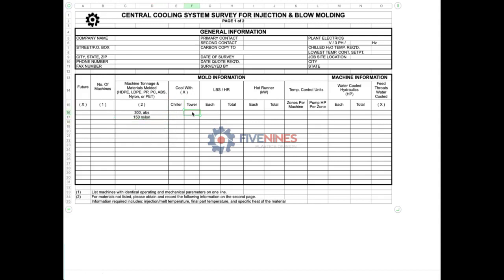You mark what it's connected to, whether it's chiller or tower, pounds per hour. So where you see 'each' here, you can list all of your 300-ton machines in this row and all of your 150-ton machines in this row. However, I suggest that you do it individually, because not only is this very helpful for working with us on addressing your system, it's also a very handy reference for you to have in the future. It's always helpful to have a list of what machines you have where, what they're connected to, what's their consumption, and so on. Just take a little extra effort and list them out individually. I think it'd be helpful for you.